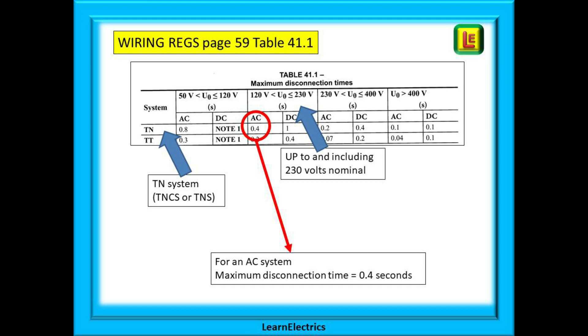We will stay with our type B 32 amp BS EN 60898 MCB. Looking at page 59 in the wiring regs book, table 41.1 shows us that during a fault a TN final circuit with a nominal voltage over 120V AC and up to and including 230V AC should disconnect within 0.4 seconds. This is to protect persons and livestock from the dangers of electric shock. Manufacturers design devices to comply with a standard stating that the device must disconnect in less than 0.4 seconds if a fault current of a certain size passes through it. Different types and sizes of breaker will have different current requirements.